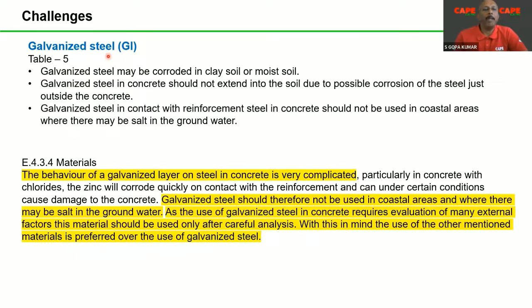Number two, what kind of material do we use? Whenever it comes to the type of material, we always talk about galvanized steel. All of you know GI, which is available very abundantly in India. Now the recommendation in the standard, table 5: galvanized steel may be corroded in clay soil or moist soil. That means if you use galvanized steel as a natural component, imagine you are making a grid under the building and your building has to be there for the next 100 years. If the GI strip or GI conductor put under the building corrodes within 10 years or 20 years or 30 years, then after 20, 30 years you have nothing on the ground. So you will be in deep trouble. Galvanized steel may be corroded in clay or moist soil, so while using natural components, you have to think twice about using GI.